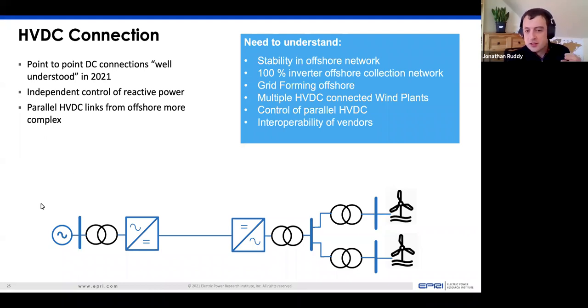But the other side of that is that our offshore system is now completely decoupled from the onshore system by the DC cable. And that means that the AC system offshore has no synchronous machines. It has no conventional way of operating the power system. So it's a fully electronic grid, and that comes with a different set of design criteria and challenges, and things like having grid forming offshore, where the actual VSC HVDC converter station needs to control that offshore grid and make sure it stays stable. Again, when you go to parallel versions of these HVDC links, that increases the complexity and increases the design challenge there.